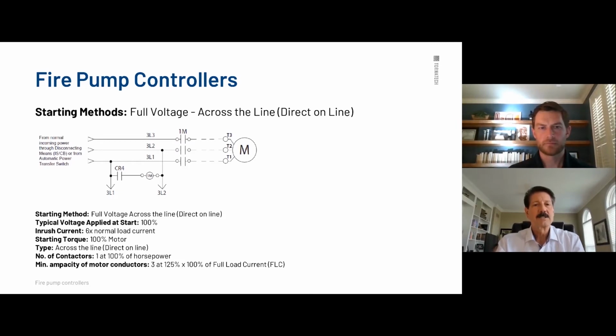So here we are, across the line. Full voltage. It's quite easy. Contactor opens and closes. Here's your 3 lines coming in. And again, T1, 2, and 3 to your motor leads right here. It's very simple. Very simple design.